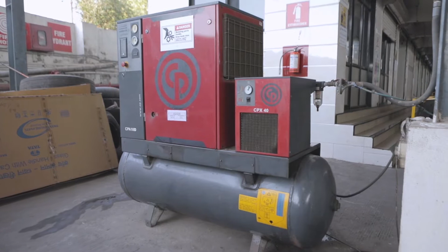Pressure vessels. As per the Factories Act, any tank containing pressure more than atmospheric pressure is considered a pressure vessel. Air compressor tanks are a common example of pressure tanks at workshops. These tanks must be tested and certified by an authorized person, approved by the Factories Inspector, as per the defined frequency in the Factories Act.